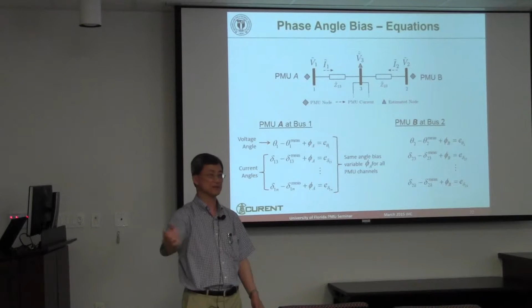The other thing we can do is look at the line currents. These are a bit more difficult because voltage measurements have a tight range, while line currents, depending on operating conditions, can be high or low—especially at low current values, which fall outside the region of linearity.